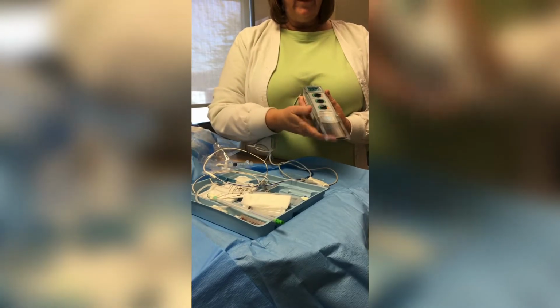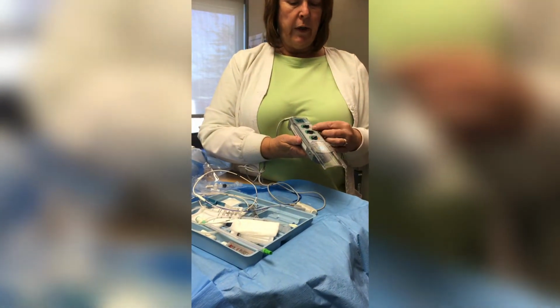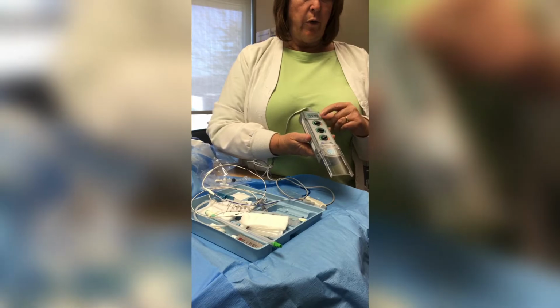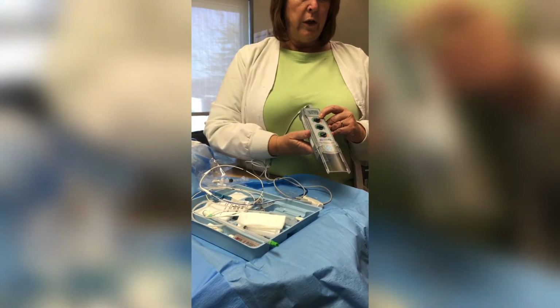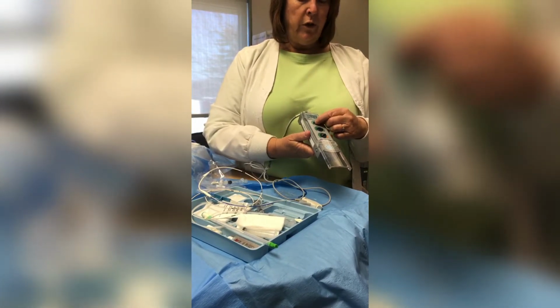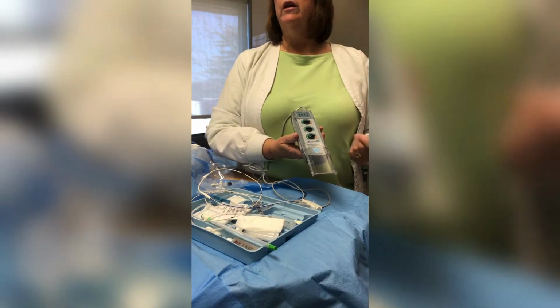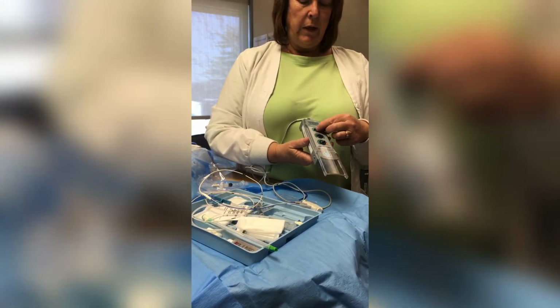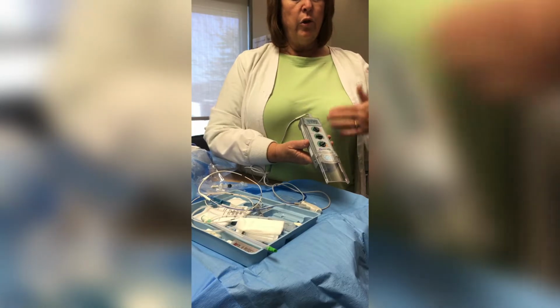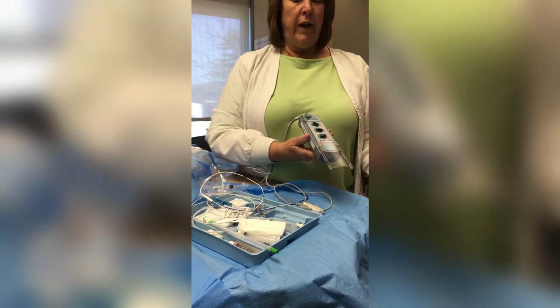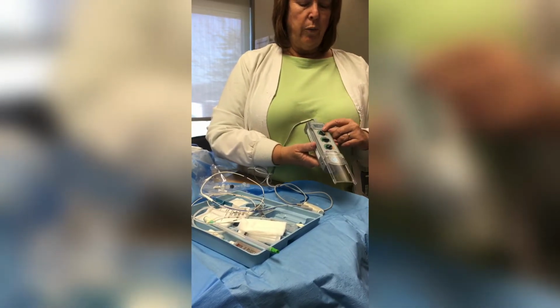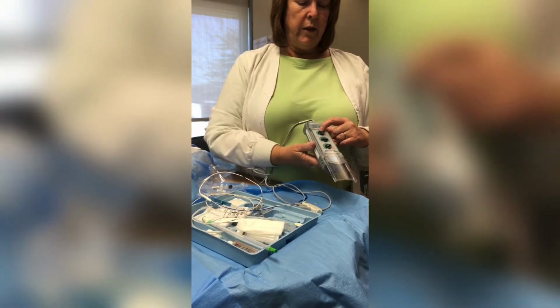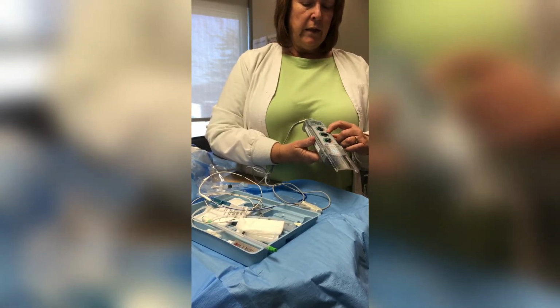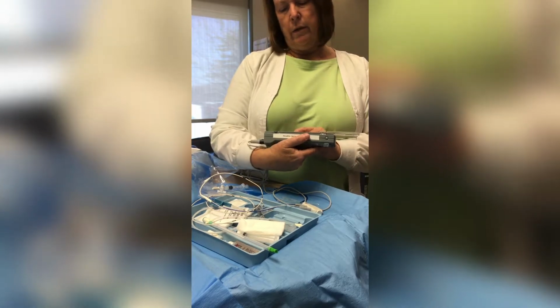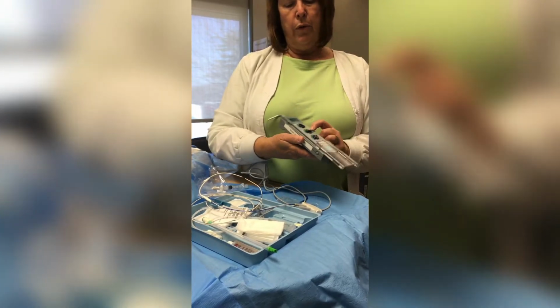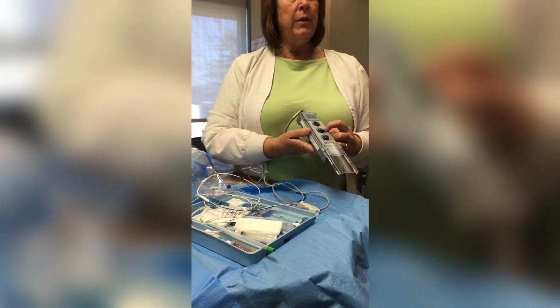The doctor will tell you when he gets the pacemaker in how fast he wants the heart rate to go. This first dial here is for heart rate. So if the patient's heart rate is 30, the doctor may say, let's put the pacemaker at 60 or 70. So when you get it in, you will pace faster than the patient's heart. So you'll preset the rate that you want the pacemaker to go. And the next dial is the output, which is the MA, milliamps, is the output.